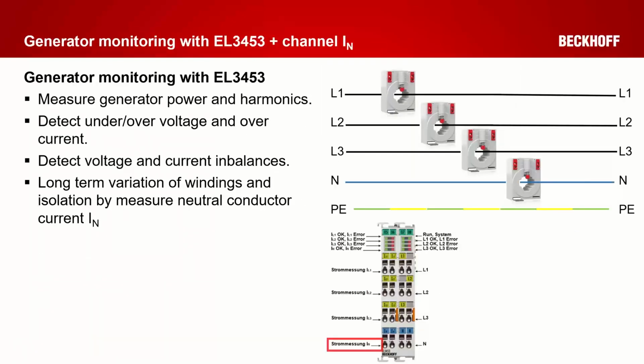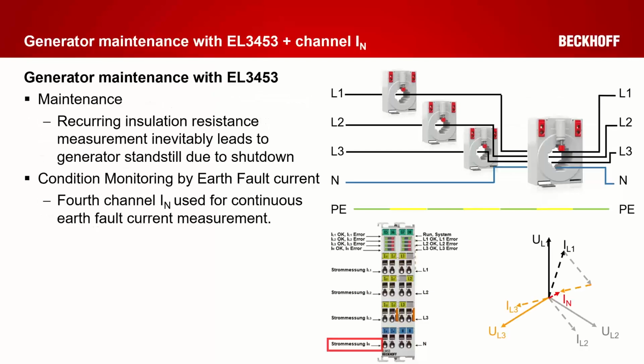Yes, another idea is using our EL3453 as the extra channel for neutral current measurement, which is almost standard. Now we're coming to our condition monitoring topic. With condition monitoring, we can detect voltage and current imbalances. That's easy. We can also protect our generator, but we can now also detect deterioration of windings and insulation errors by measuring the neutral conductor current. As an alternative, we can also measure the earth fault current by summing all phase and neutral currents together. And this is also a good condition monitoring feature for long-term analysis of our generator.